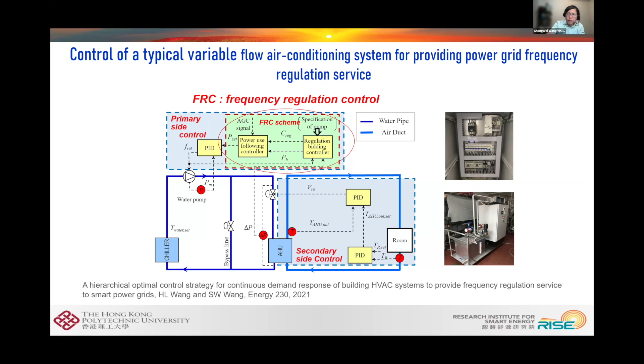Originally, without introducing this strategy, the supply temperature to the spaces could change by 4 to 8 degrees Celsius, which caused the temperature in the space to vary too much. After we introduced this frequency disturbance compensation scheme, we reduced the supply temperature variation to less than 2 degrees. A 2 degree variation in supply temperature does not cause too much disturbance to the temperature control of the space.